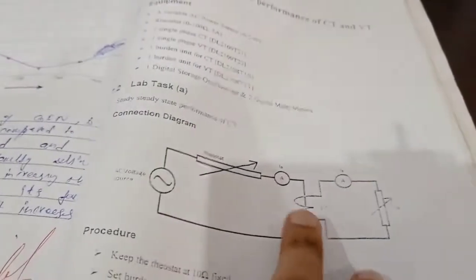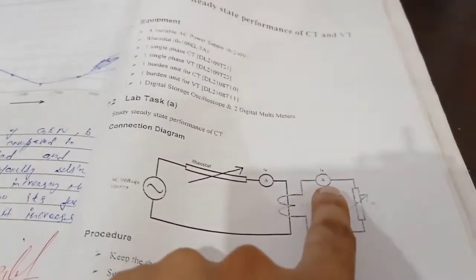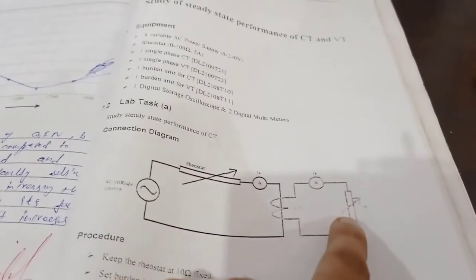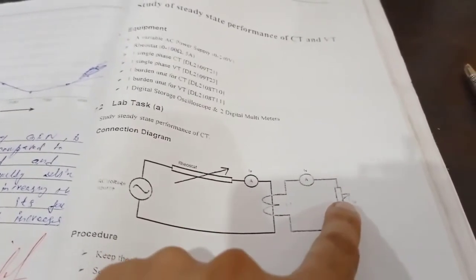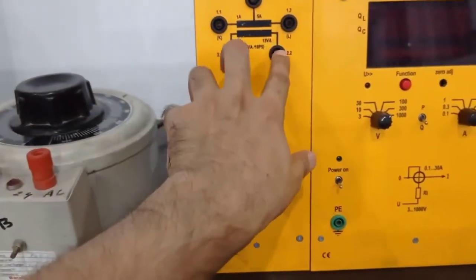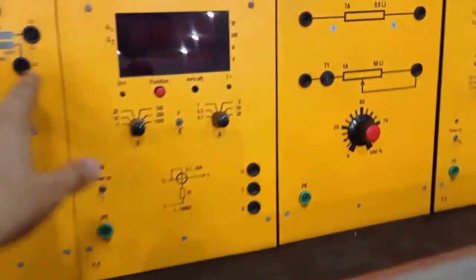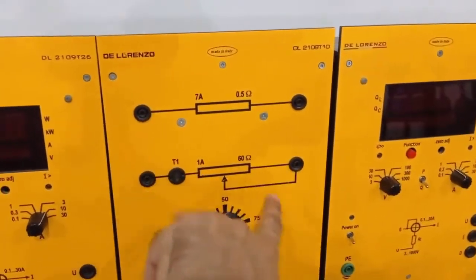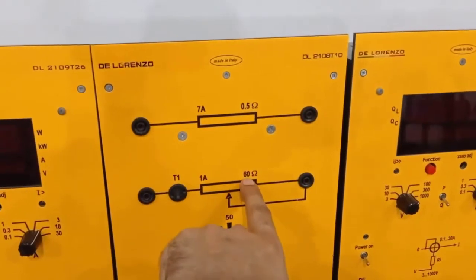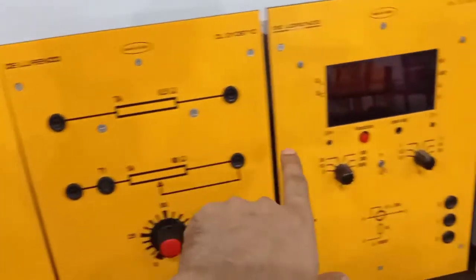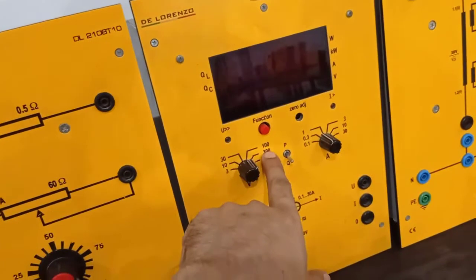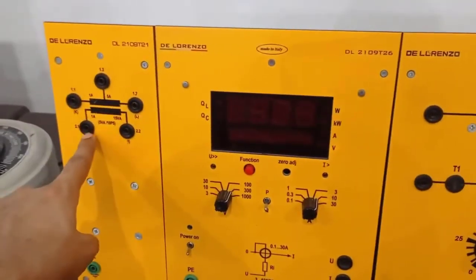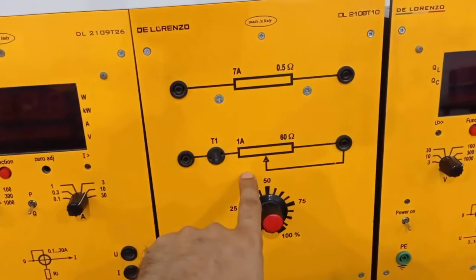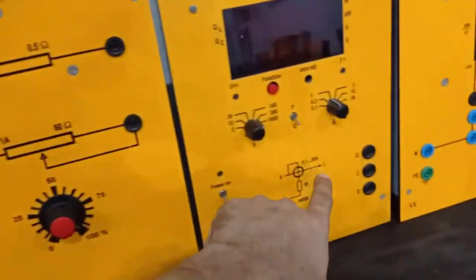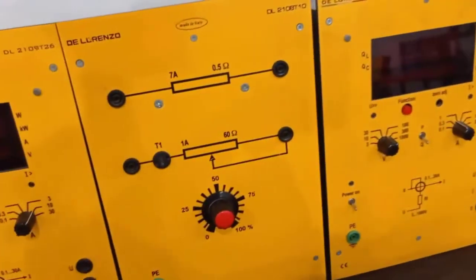Next, on the secondary side, this is the secondary winding of the CT. Here we have an ammeter and a variable resistance, a variable burden, connected across the secondary of the current transformer. The maximum value of that variable burden is 60 ohm. Another ammeter will be connected on the secondary side. It means the secondary of the CT, this variable burden and this ammeter will be connected in a single loop.